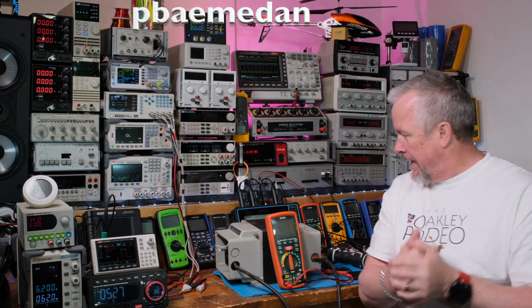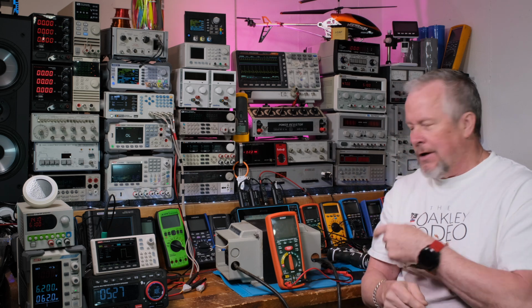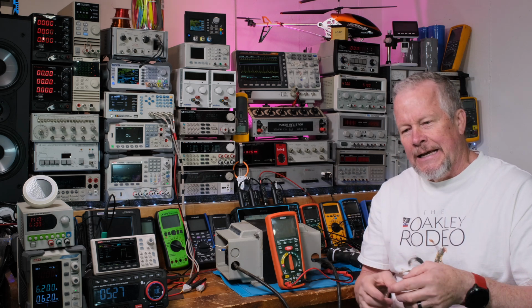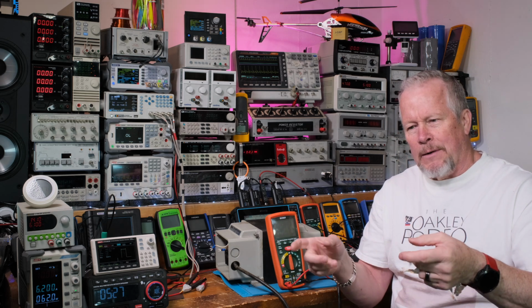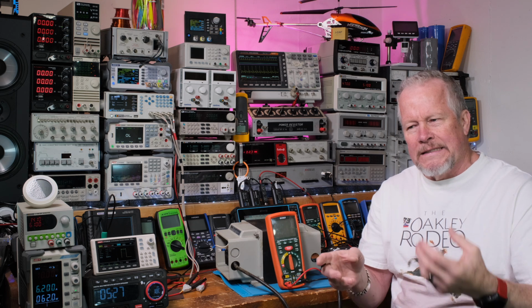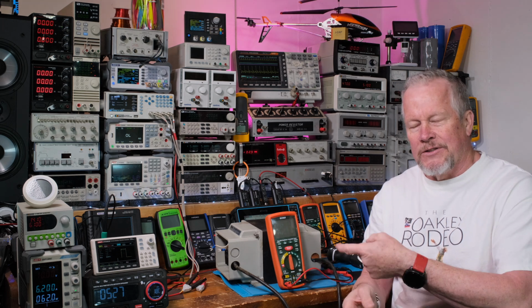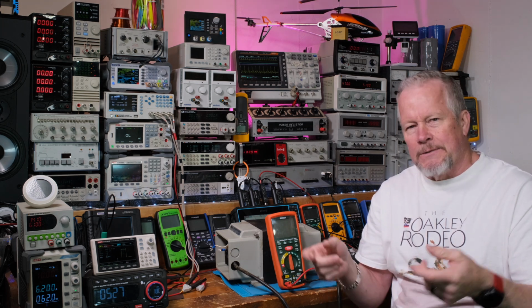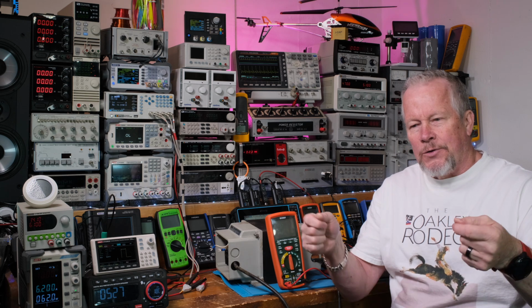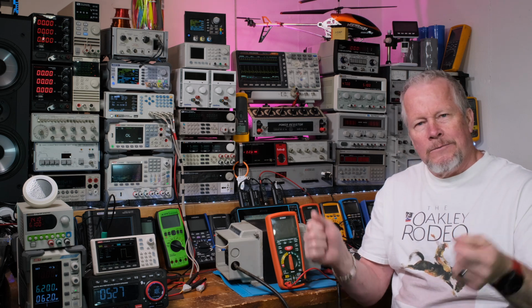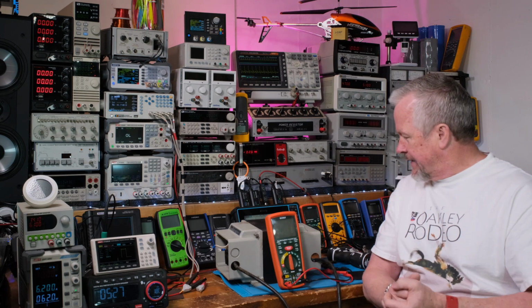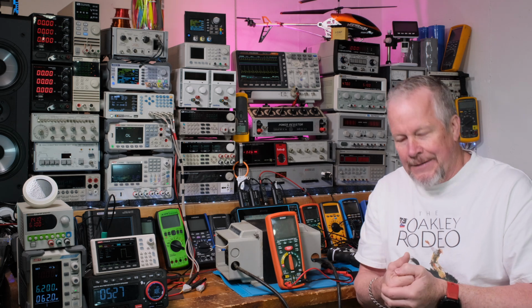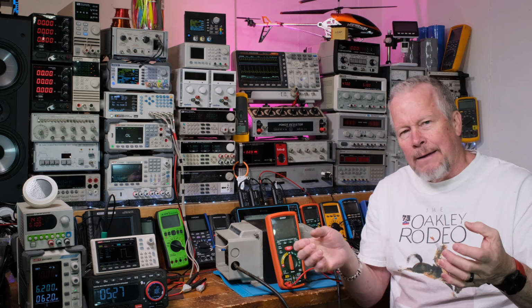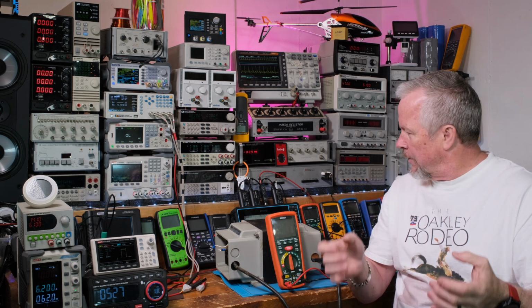But I'm glad I found those neutral to ground connections. They might have had that problem and then disconnected one of the windings, not realizing what the problem was, thinking it was the transformer, when it was really just because they're bonding that screen/neutral wire on each side to chassis. So I don't know, it's a mystery, but I'm going to do a little more checking before I feel totally comfortable with it.